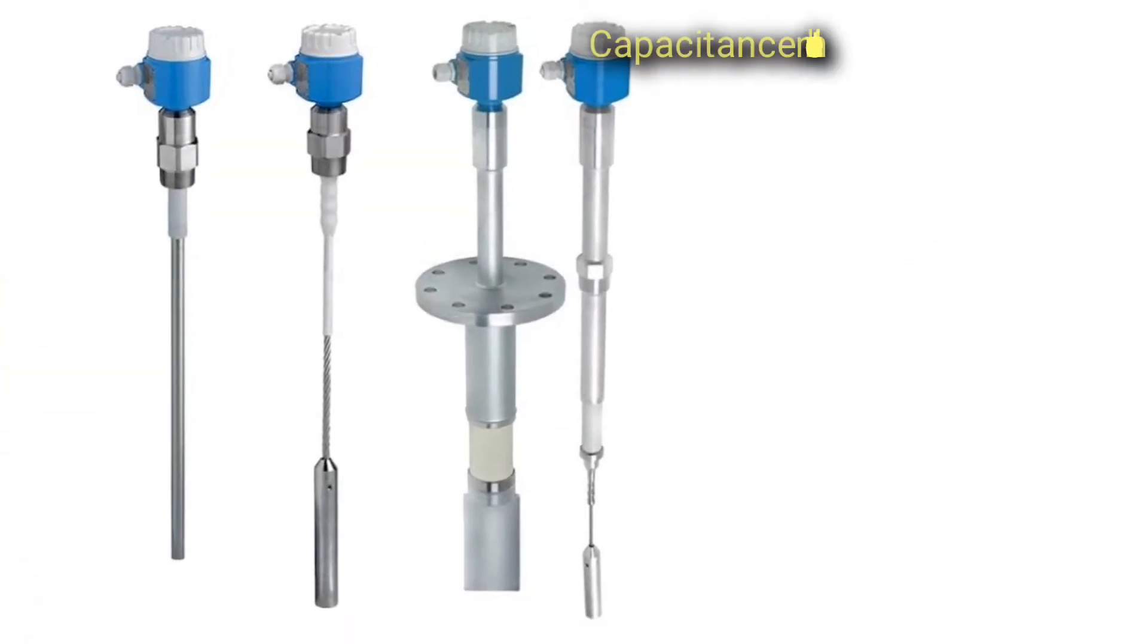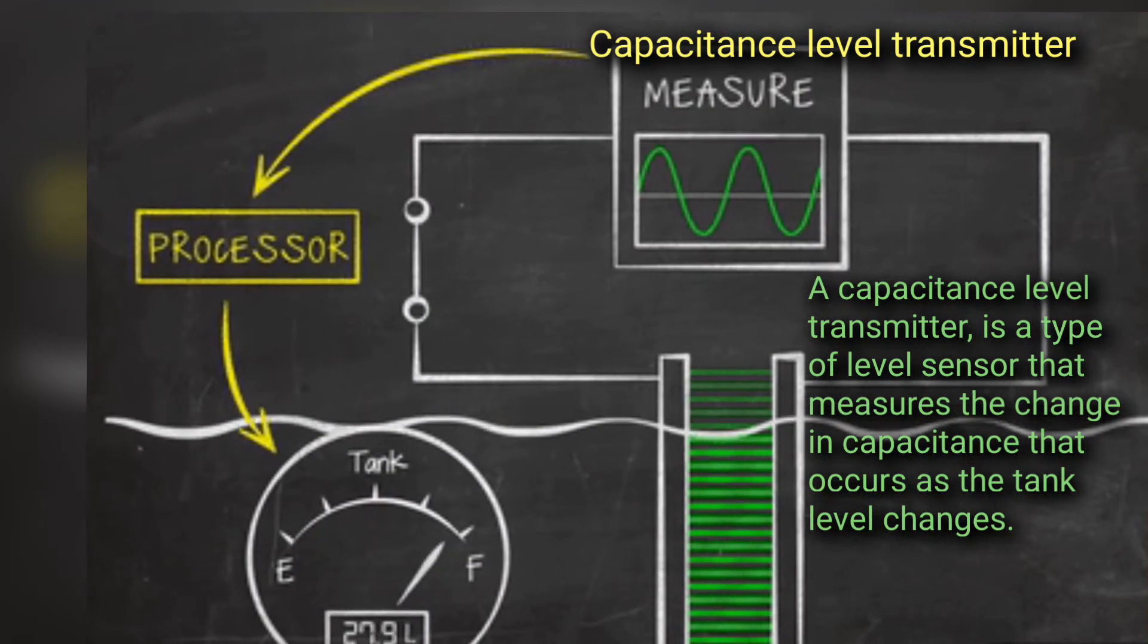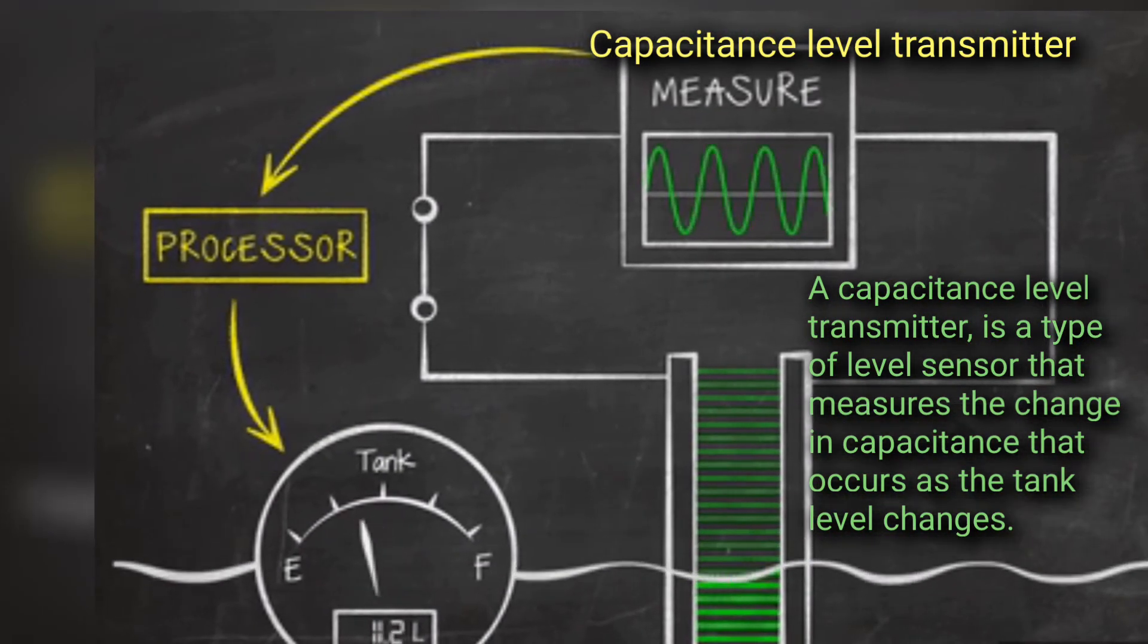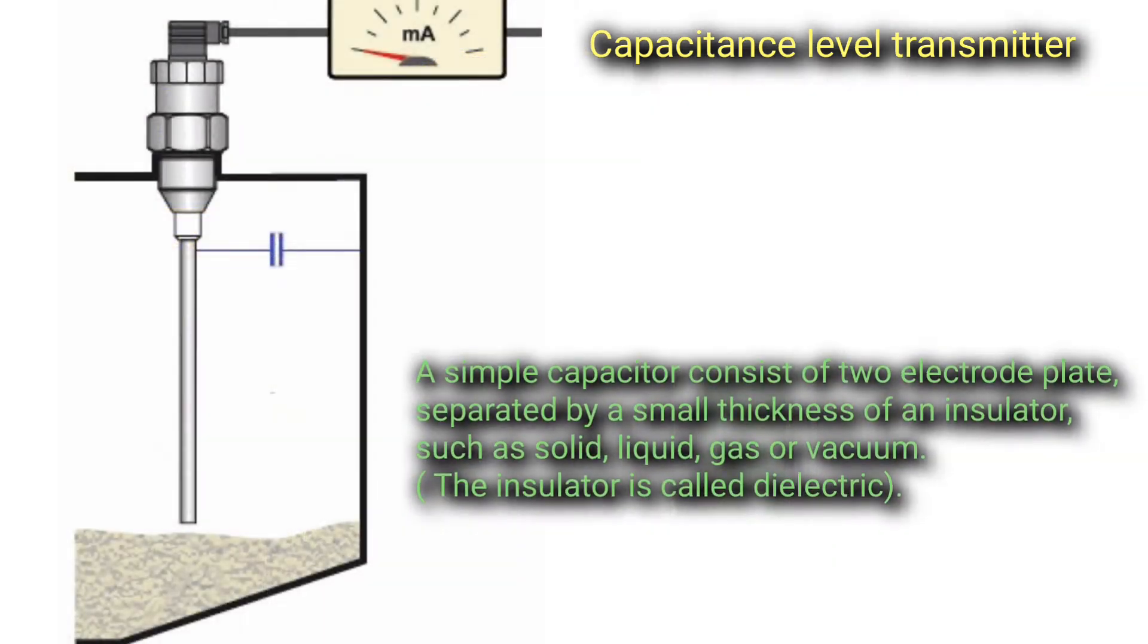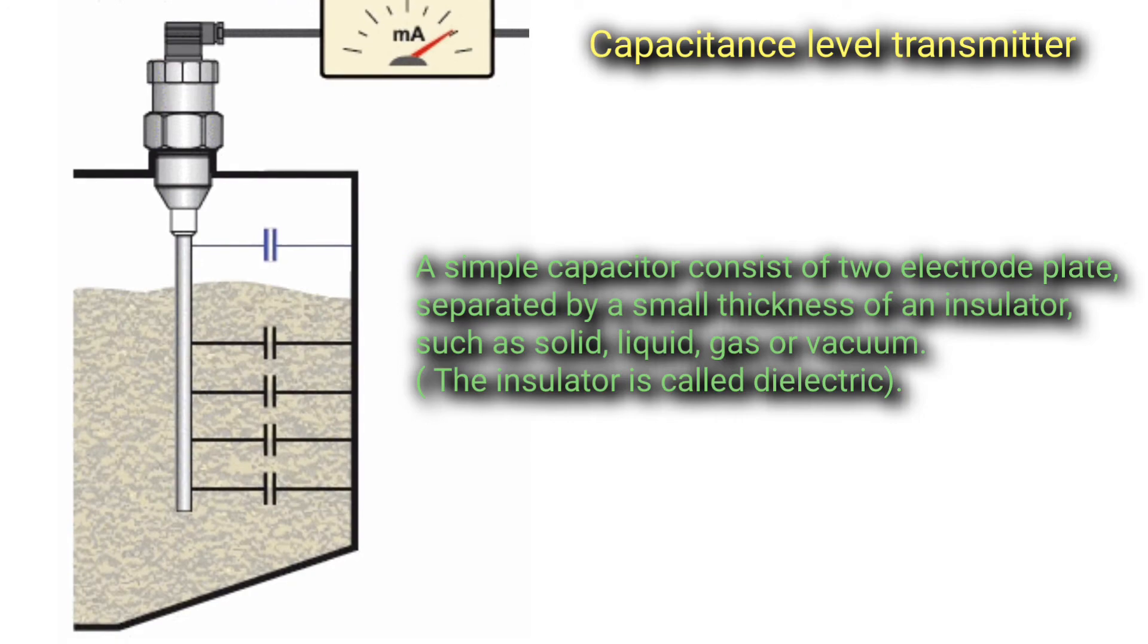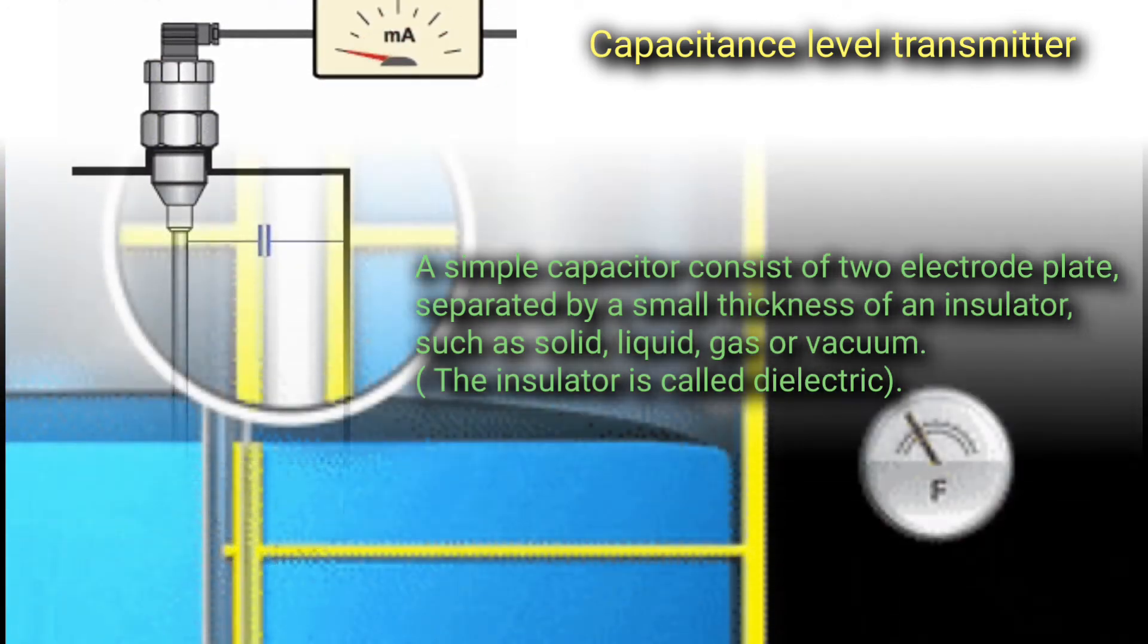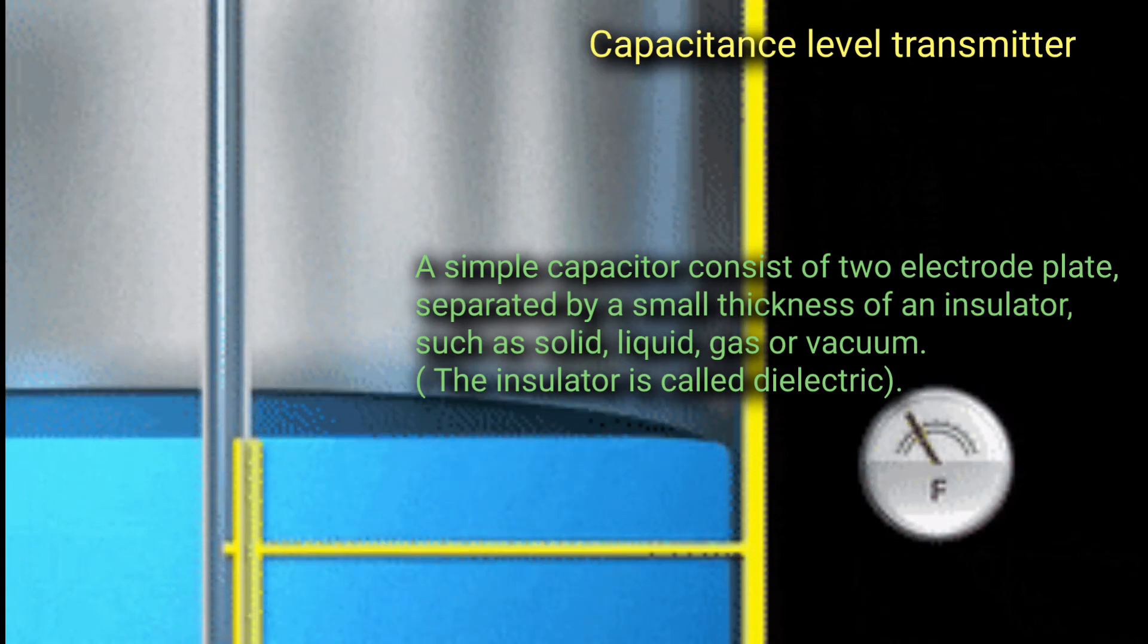Capacitance Level Transmitter. A capacitance level transmitter is a type of level sensor that measures the change in capacitance that occurs as the tank level changes. A simple capacitor consists of two electrode plates separated by a small thickness of an insulator such as solid, liquid, gas, or vacuum. The insulator is called dielectric.